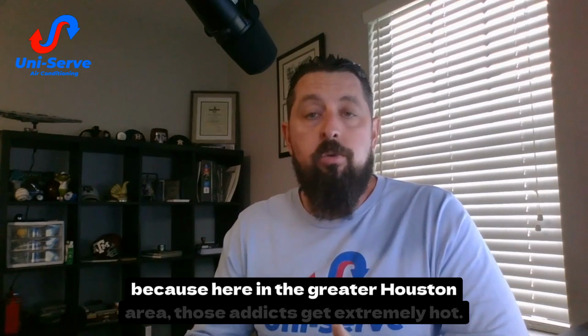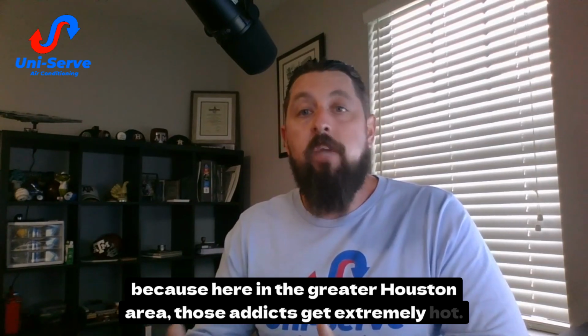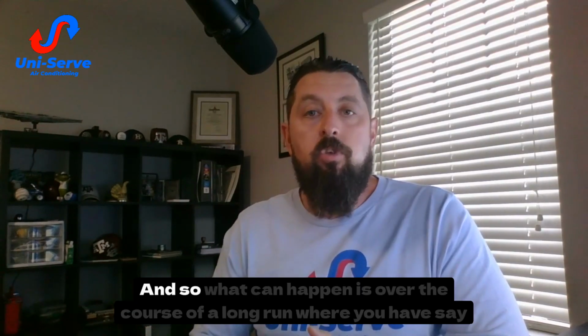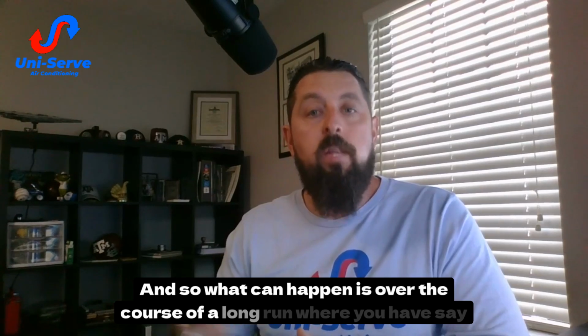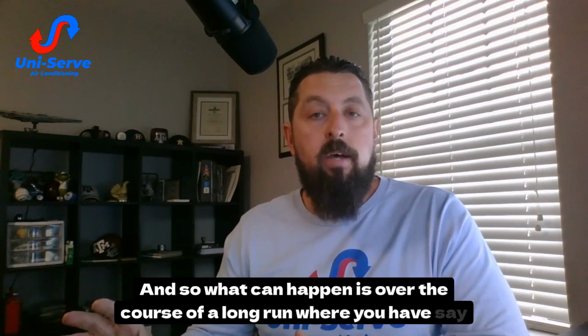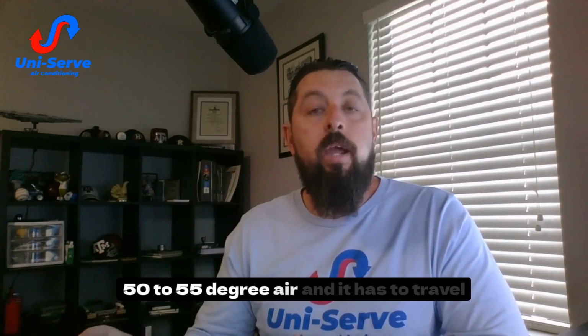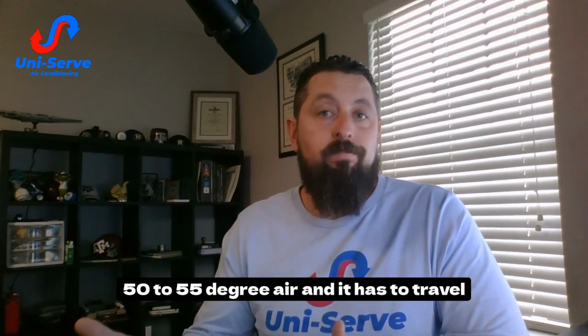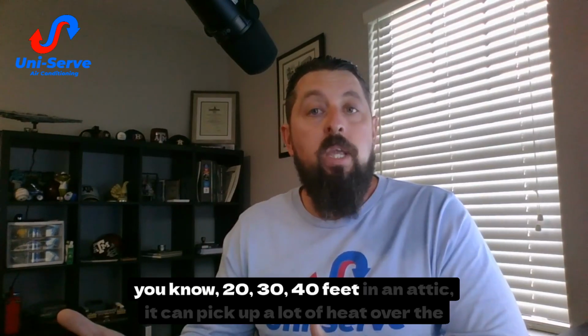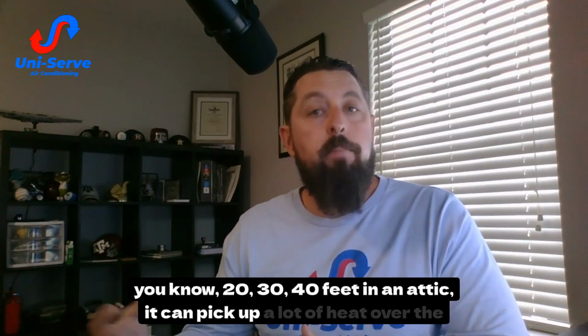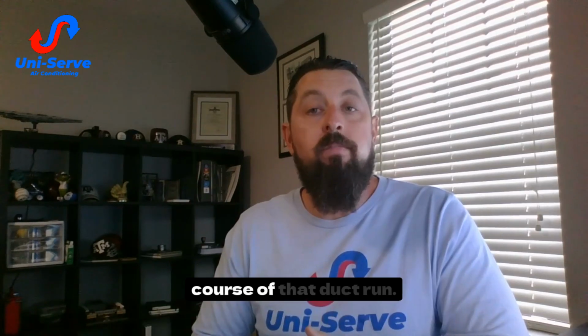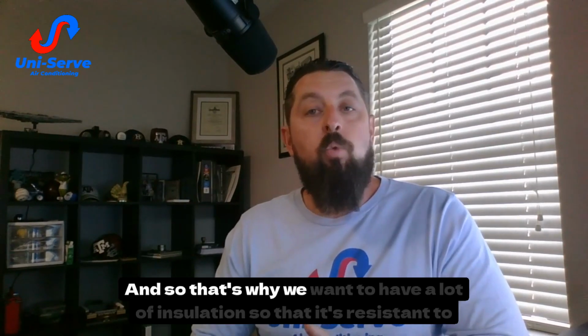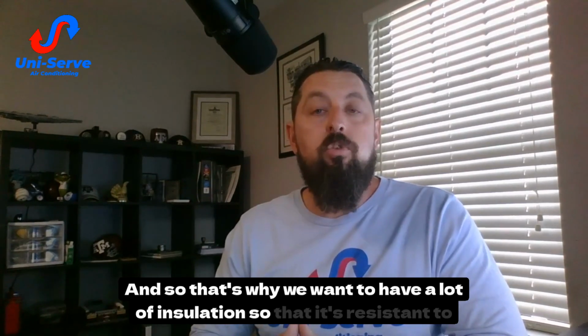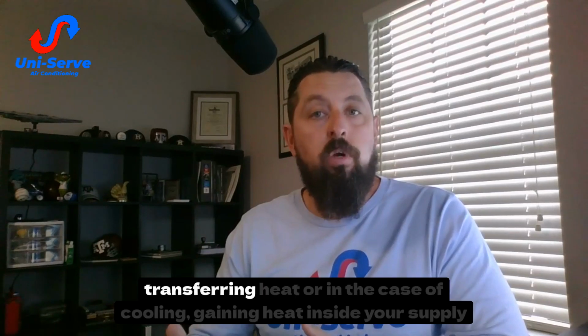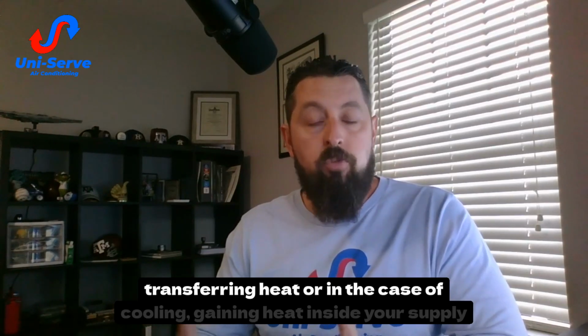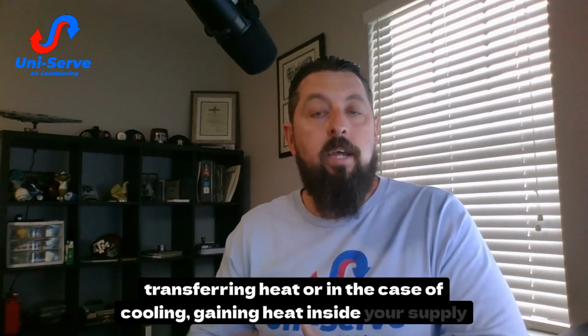Because here in the greater Houston area, those attics get extremely hot. What can happen is, over the course of a long run where you have, say, 50 to 55 degree air, and it has to travel 20, 30, 40 feet in an attic, it can pick up a lot of heat over the course of that duct run. That's why we want to have a lot of insulation, so that it's resistant to transferring heat, or in the case of cooling, gaining heat inside your supply airflow.